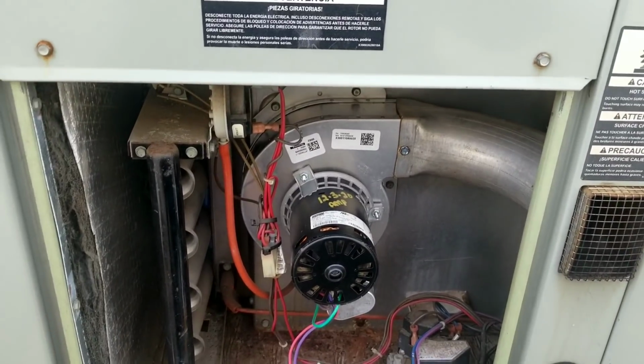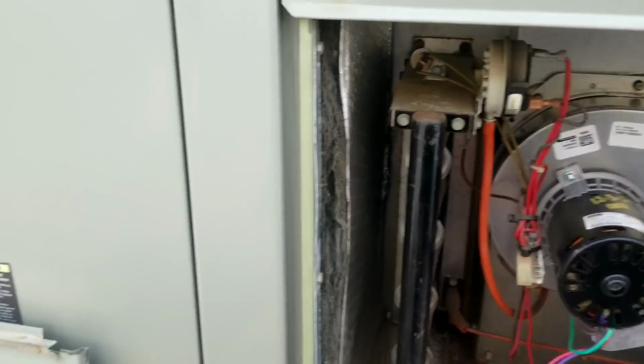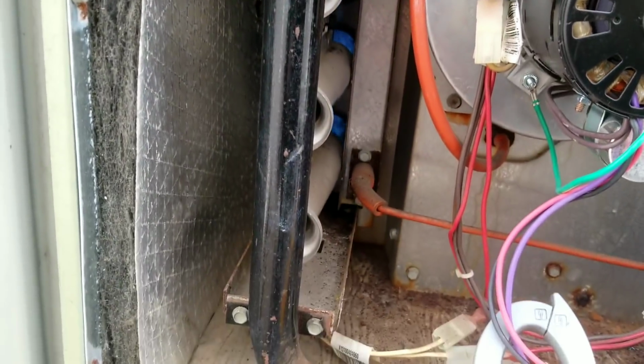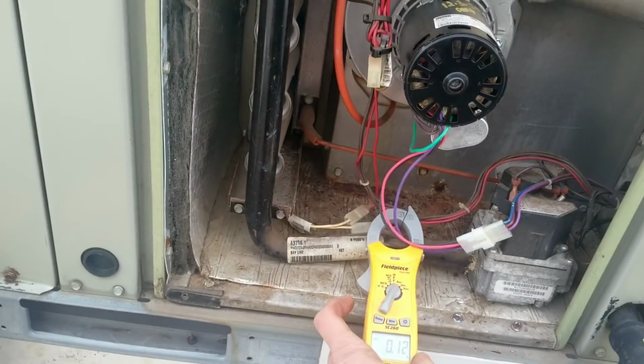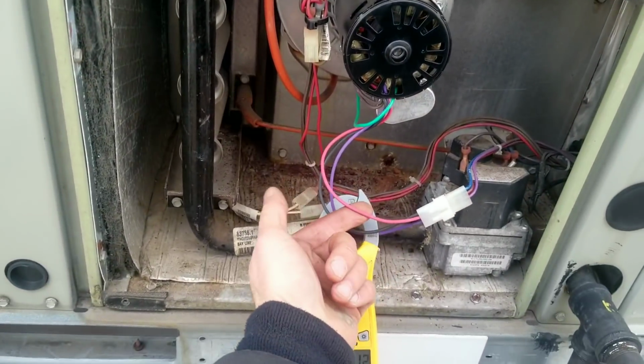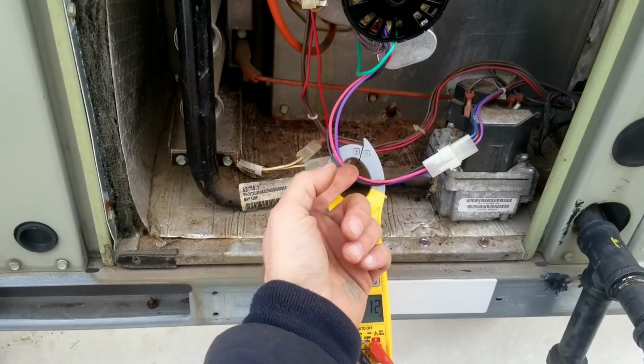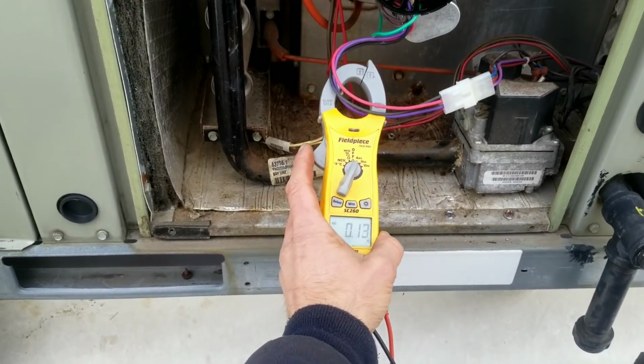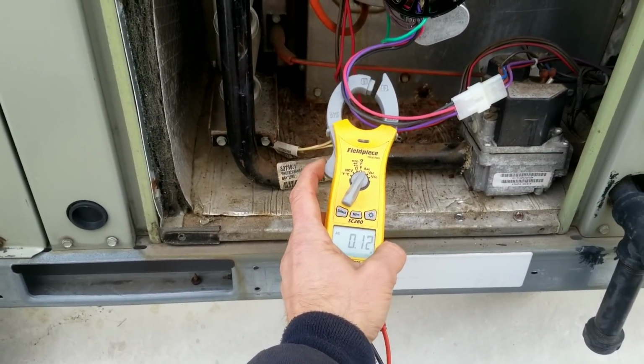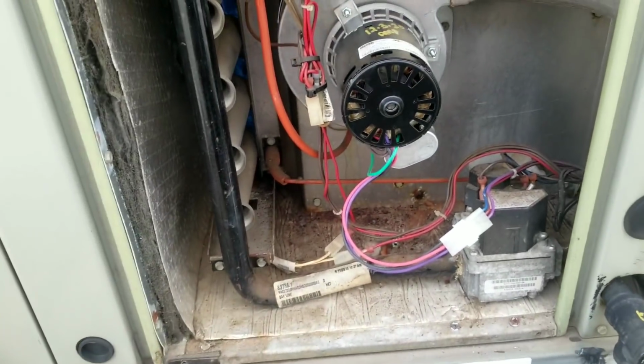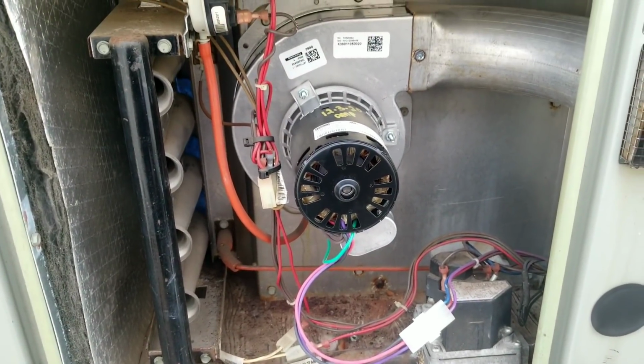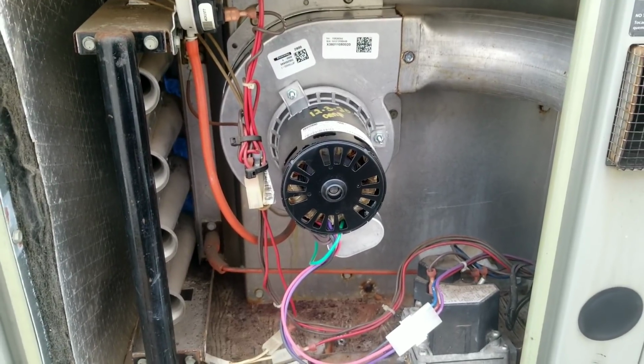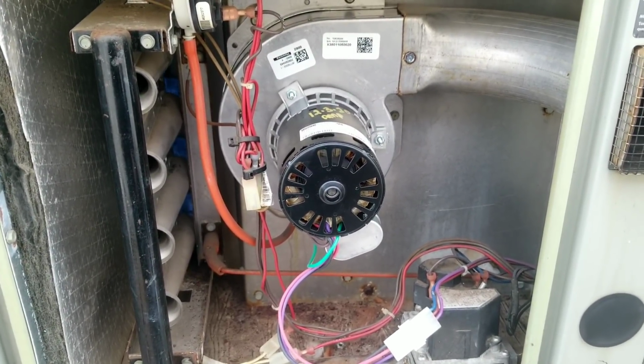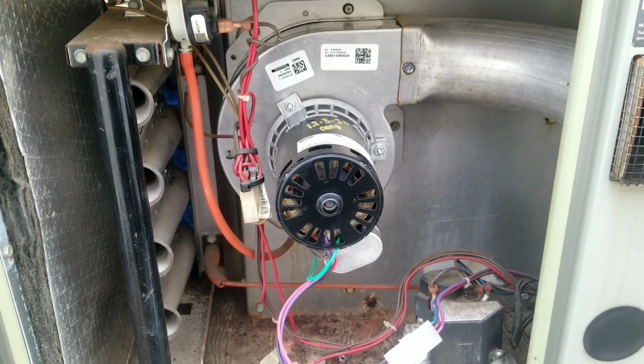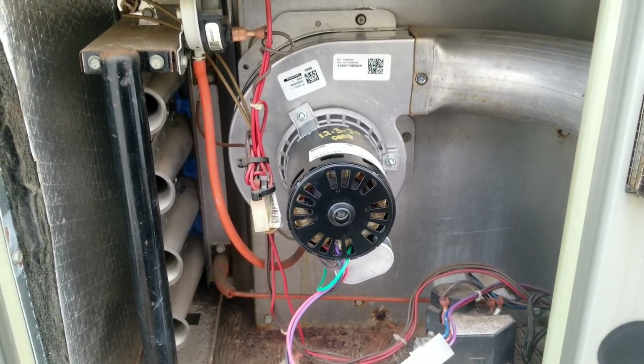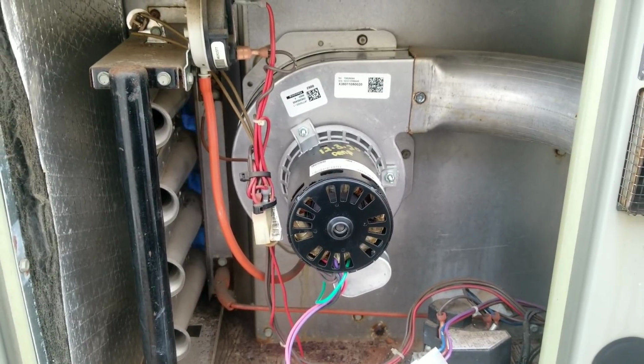Alright guys, 37 hours later, the unit is up and running. It did fire up, you can see back there. My amp draw on the high wire was initially 0.26, and it dropped out and kicked onto our low fire, which is 0.13. Now it's making a little bit of noise coming from the bearing, which is kind of alarming. I'm chalking it up right now to it being very, very cold, and I'm waiting to see if that motor warms up and the bearing noise goes away.